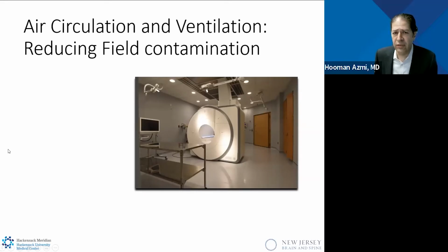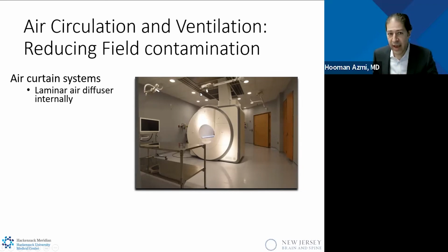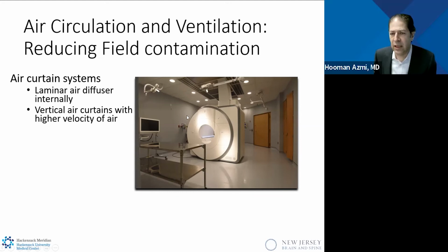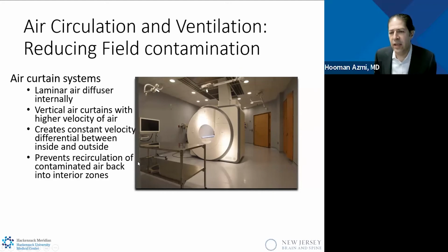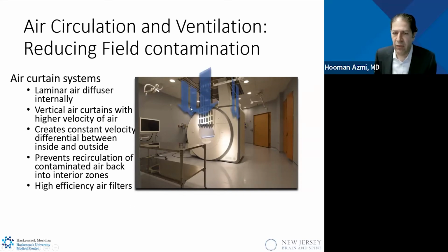So for air circulation and ventilation in the OR, there is a lot of data that shows air curtain systems are required. What are those? There are laminar air diffusers that direct the air straight down internally, and there are air curtains, and you see these guys out here. What they do is produce higher velocity air, higher than the middle air diffusers. That creates a constant velocity differential between inside and outside the curtain, and this prevents recirculation of contaminated air back into that space. And of course, we use high efficiency air filters. And this is a schematic of what that may look like, where there's higher velocity air developing a curtain around the middle parts of the air diffusers.